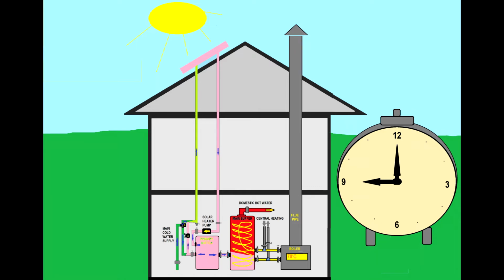When the hot water is used, the main cold water will push the fresh water into this solar panel heat exchanger and will come back into this primary buffer, and then will continue its journey into the main buffer. But the water which goes from the primary buffer into the main buffer is warm. If you look at the bottom of this main buffer, the water comes in already warm, heated up. And the boiler will only have to increase the water by 20 degrees, from 50 to 70. So sometimes you'll be able to save even 70% of the energy you waste to heat the water.